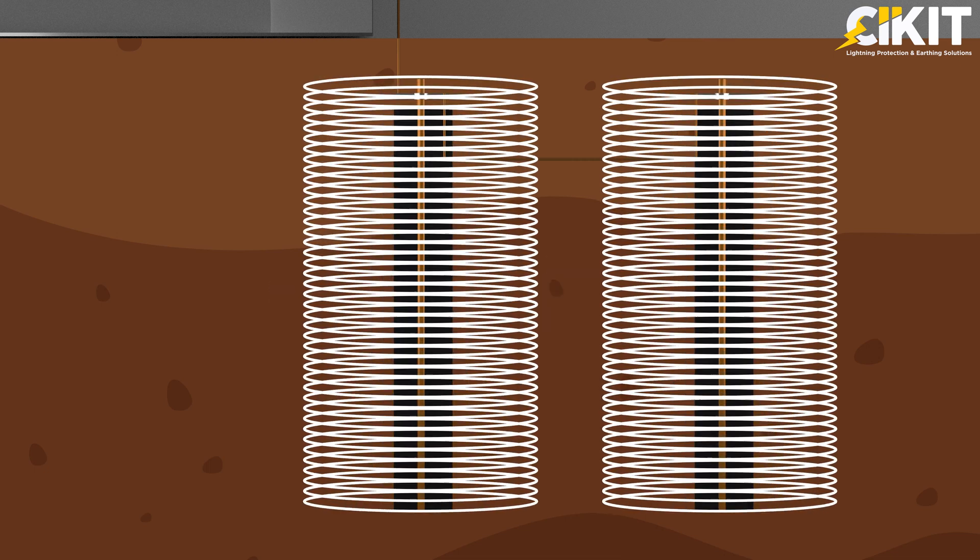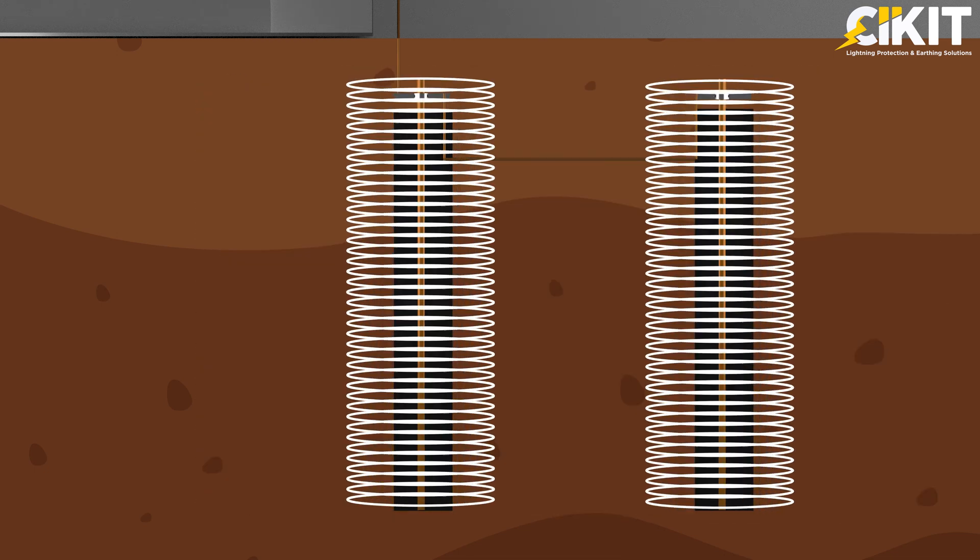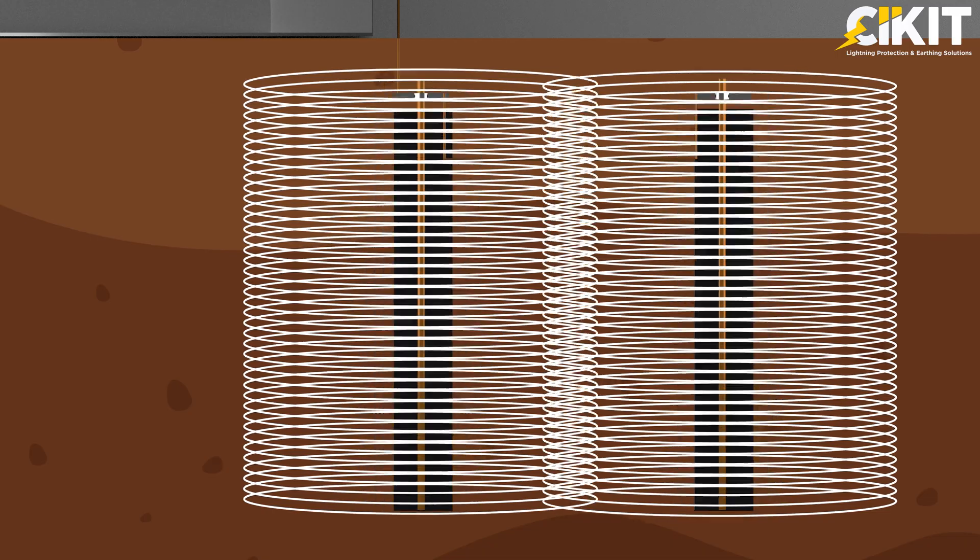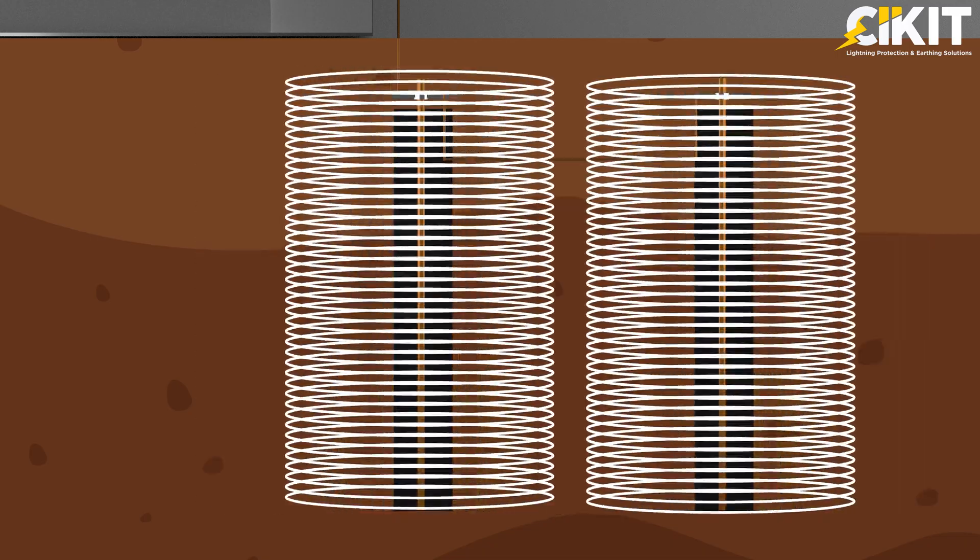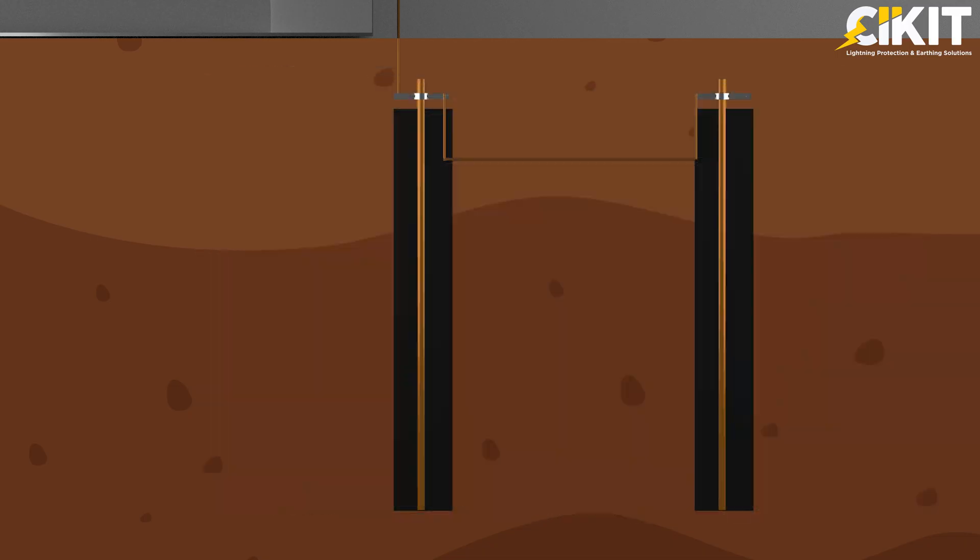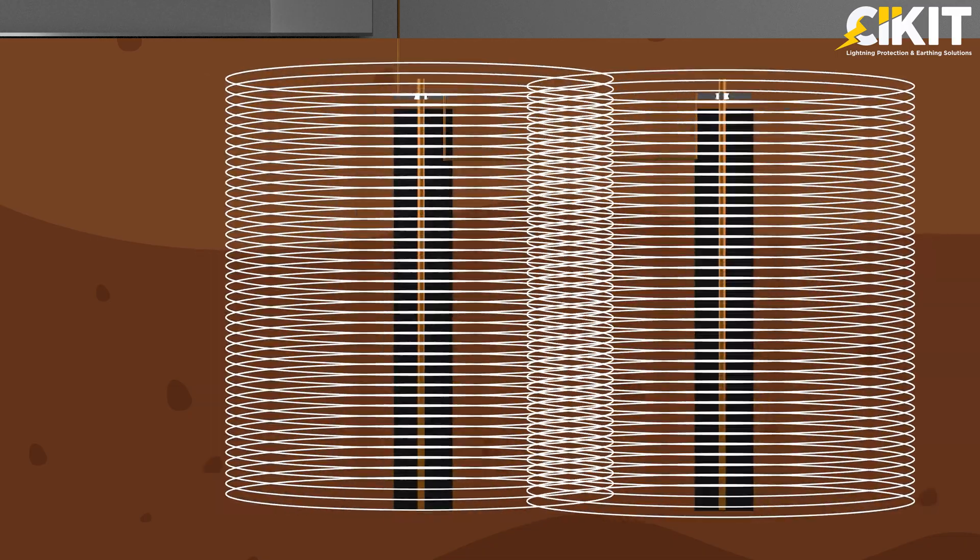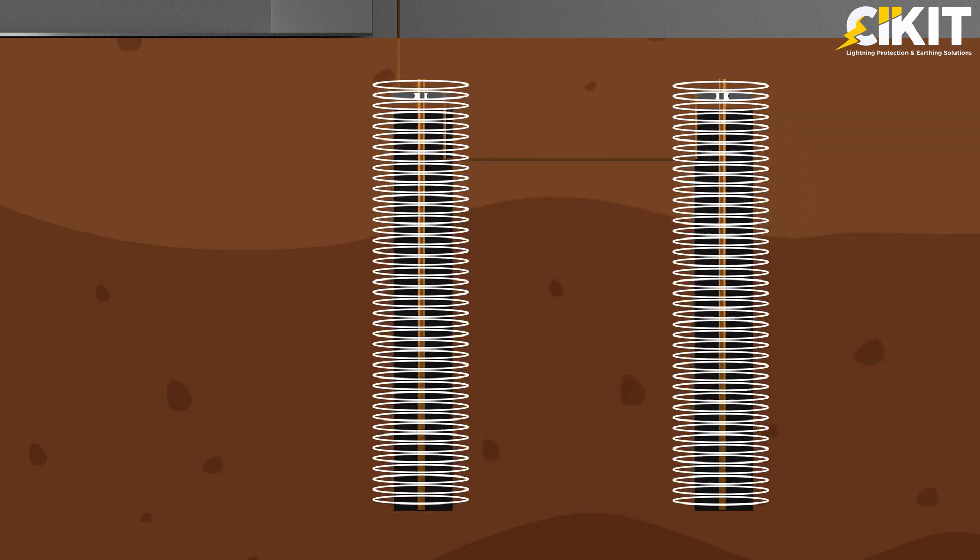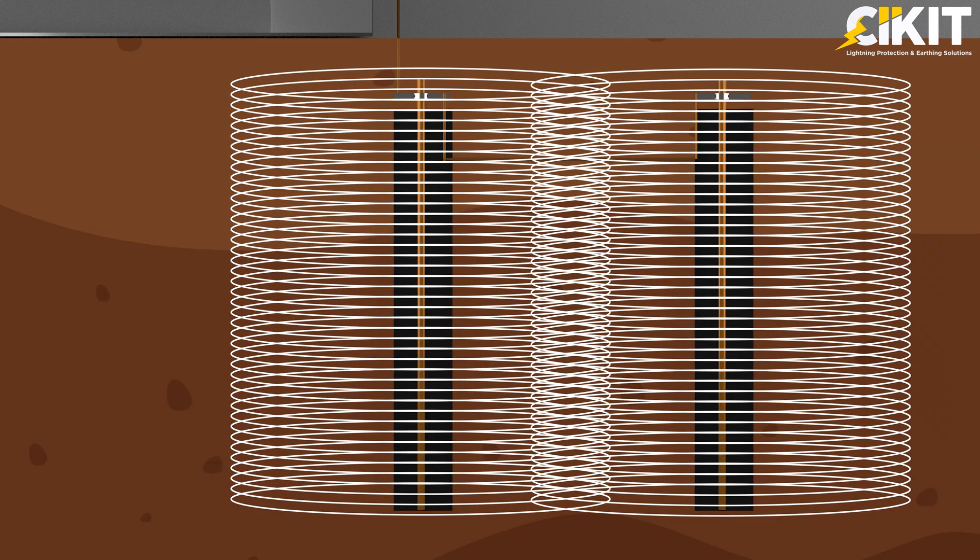If we are not providing adequate spacing, then the discharge from one earth electrode will overlap with another electrode. Because of this overlapping, the performance of the earth electrode will be reduced. The earth electrode will not be utilized to its full potential if the spacing is not sufficient.